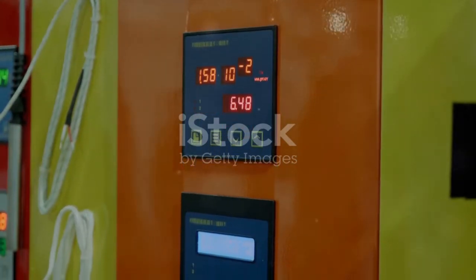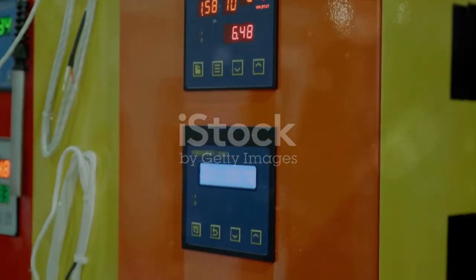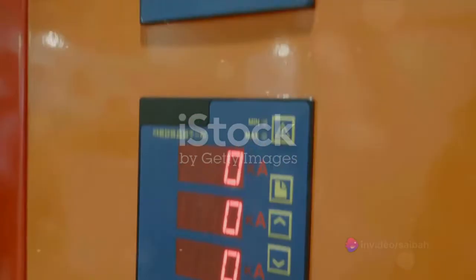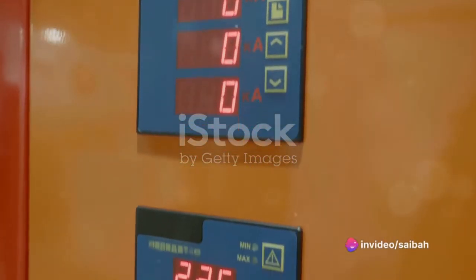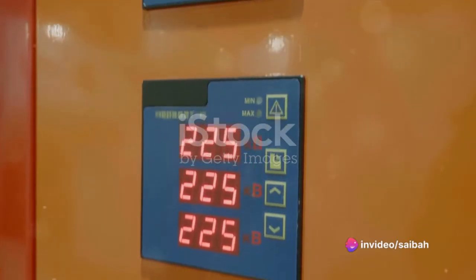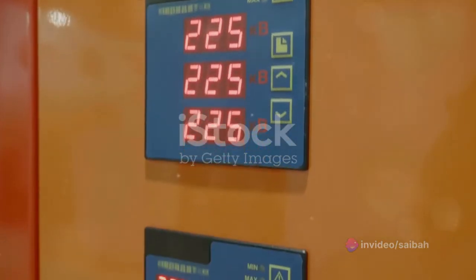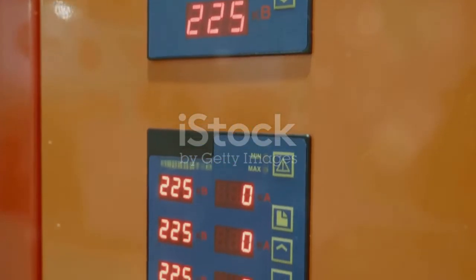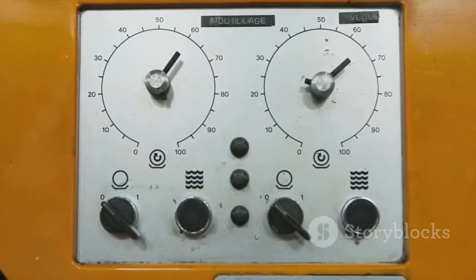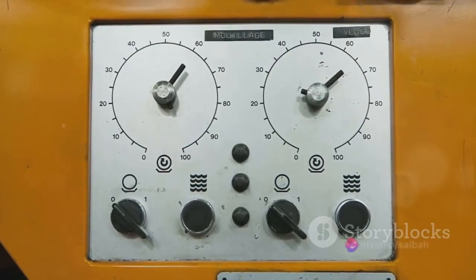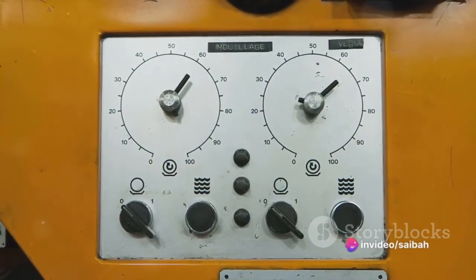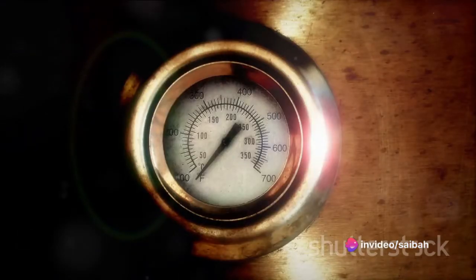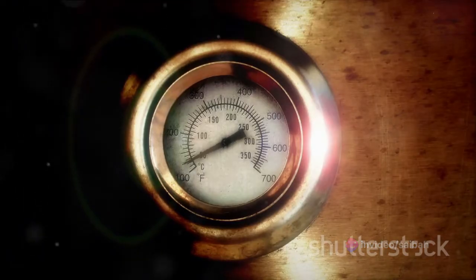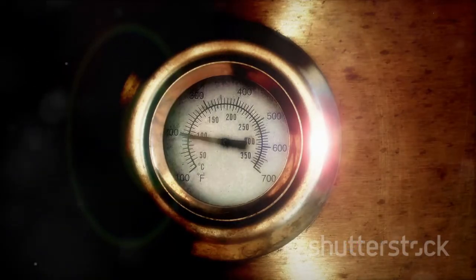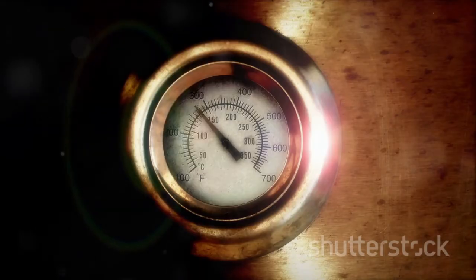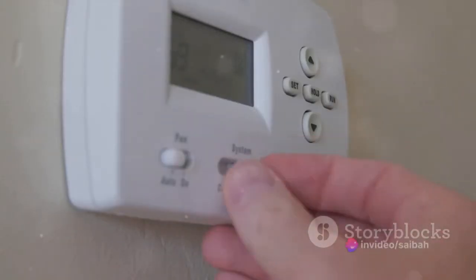There are two main methods of temperature control: PID control and on-off control. PID control, which stands for proportional integral derivative, is a type of control that uses a complex mathematical formula to maintain a constant temperature. The PID controller continuously calculates the difference between the desired temperature and the actual temperature, then adjusts the output to minimize this difference. It's like having a very skilled driver who's constantly adjusting the steering wheel to stay on course.